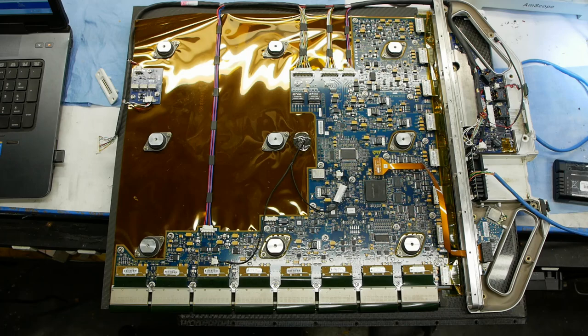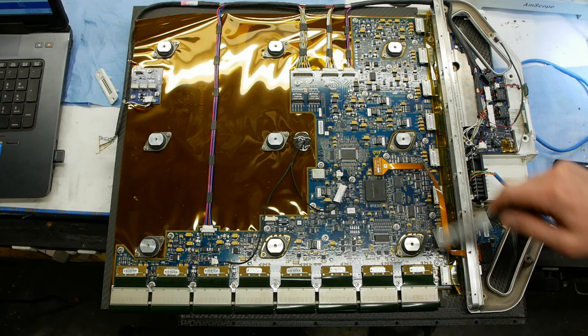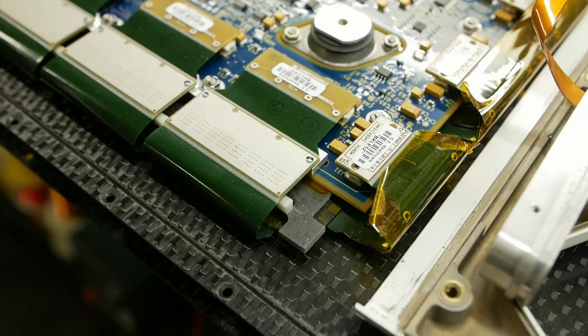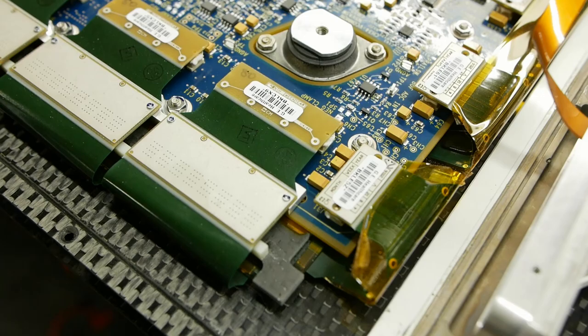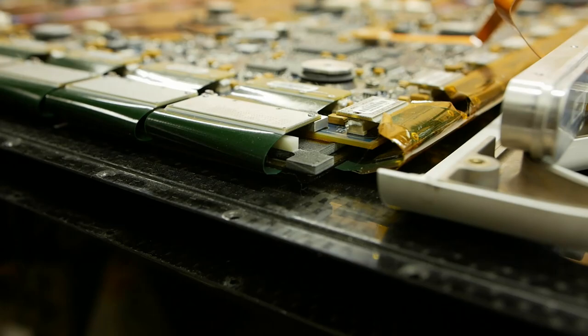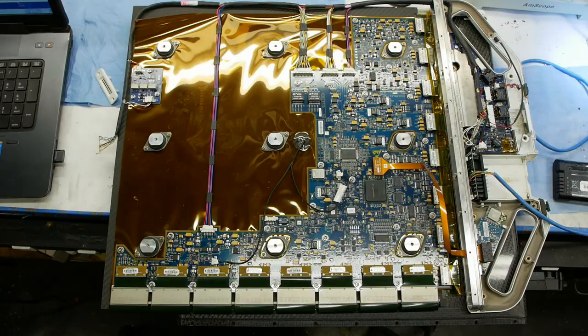This is kind of a fun thing to tear down because it's so unlike consumer electronics. No expense is spared in here. We have very expensive components, hermetically sealed ceramic packages. It's even got these really cool shock mounts to mount this whole thing inside the carbon fiber case. Then it has a carbon fiber stiffener X-ray absorber between the circuit board and the actual detector. But let's just start going through some of these components here.